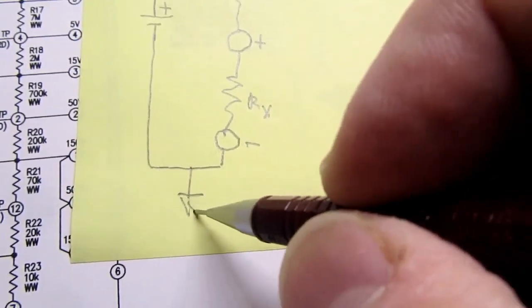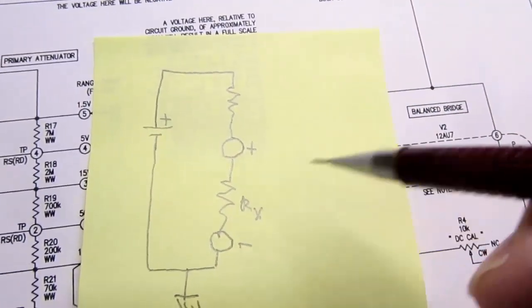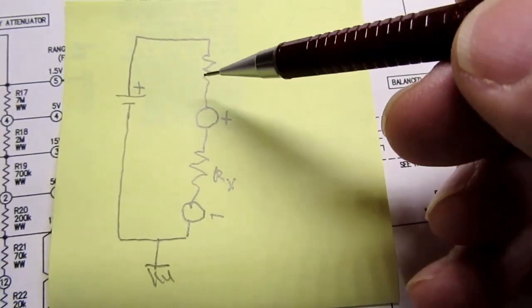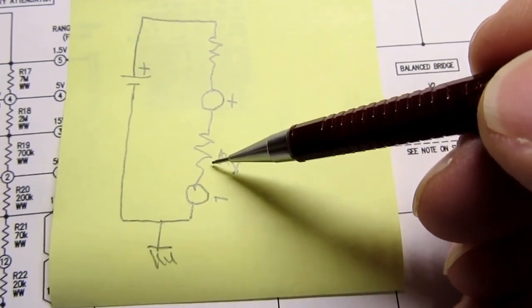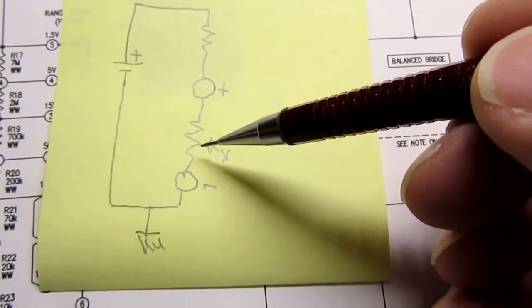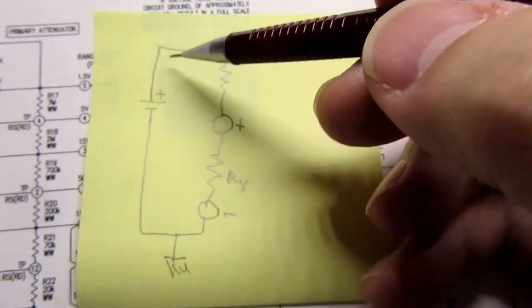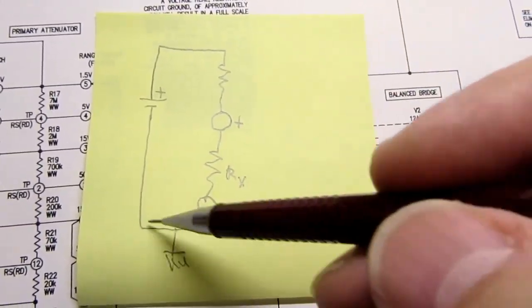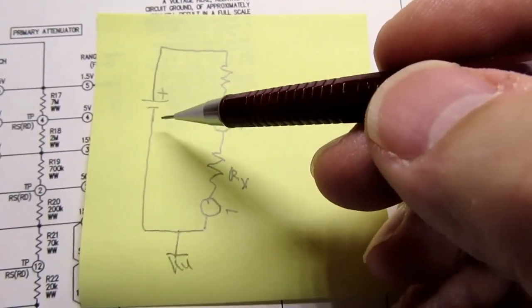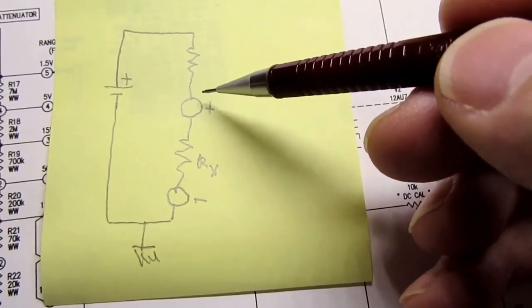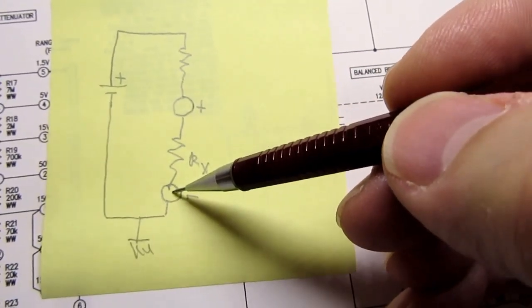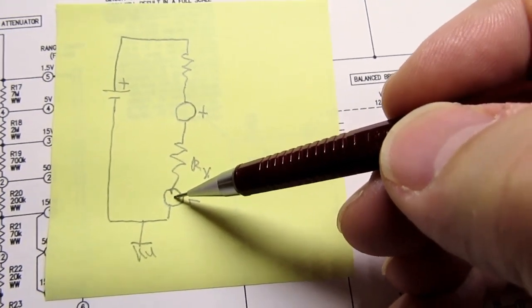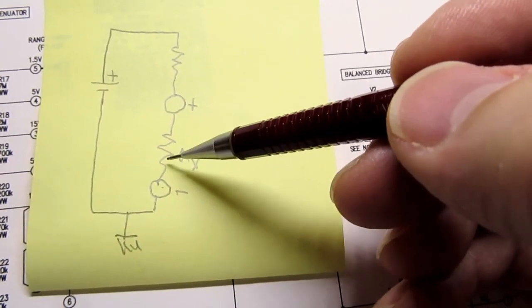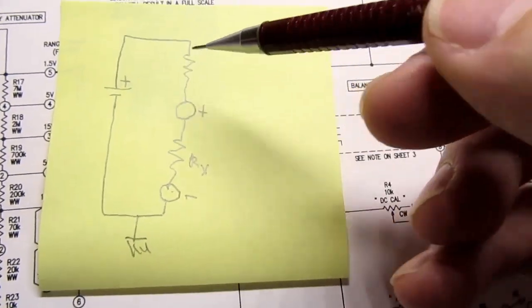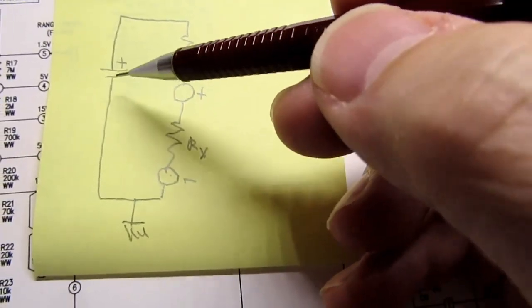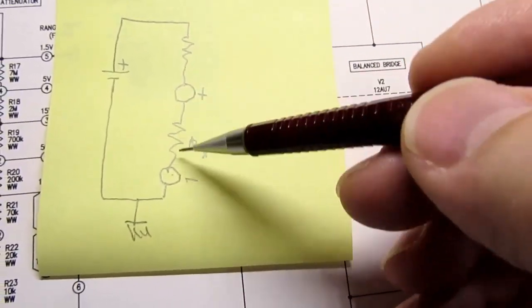This happens to be circuit ground, but we have a loop here. It's a simple voltage divider with the fixed resistor at the top and the presumably variable resistor under test on the bottom, and that causes a certain amount of current to flow through this loop from the excitation voltage of 1.5 volts. The voltage drop across here depends upon what this resistance is, but because this is not a constant current source, in other words, the current here will vary depending on what this resistance is.